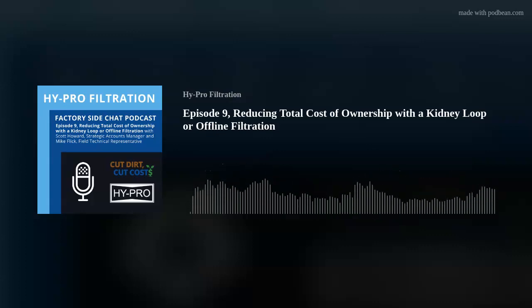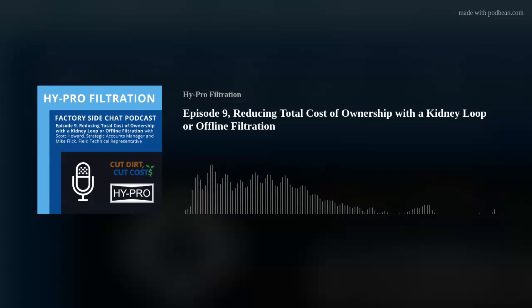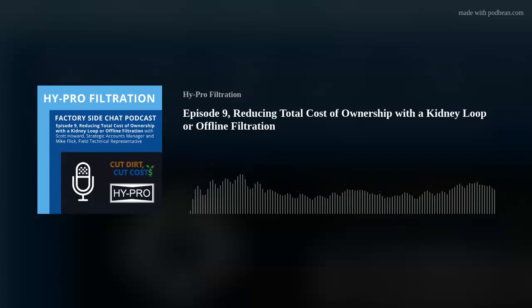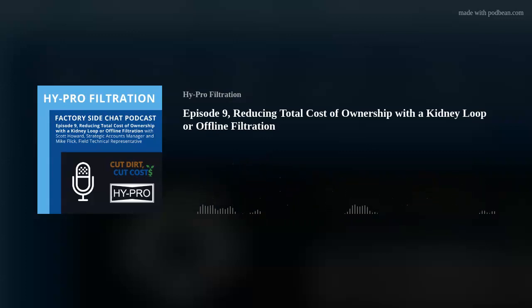That is a factor in how many times we're going to turn the tank or the system on a daily basis. And then based on that, we size the filter housing accordingly because we want to start the filter element with a low differential pressure clean in order for it to be able to capture a lot of dirt and go a longer period between change intervals. So the customer, the end user, doesn't have to worry about changing the filter elements as often, so less maintenance hours involved as well. This is all part of our total cost of ownership management.